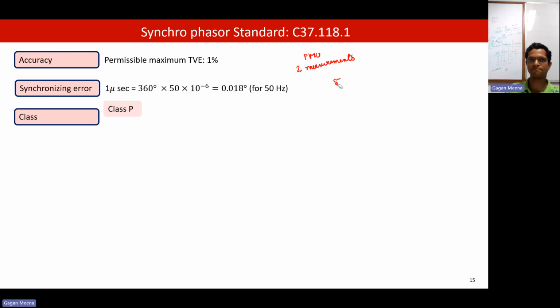For 50 Hertz, the maximum synchronizing error can be 1 microsecond, whether it is 50 or 60 Hertz. This 1 microsecond translates to 360 into 50 into 10 to the minus 6, which gives 0.018 degrees. This is the maximum permissible error. Similarly, we can calculate it for 60 Hertz also.